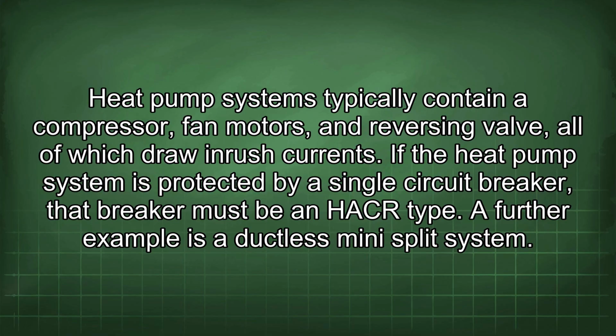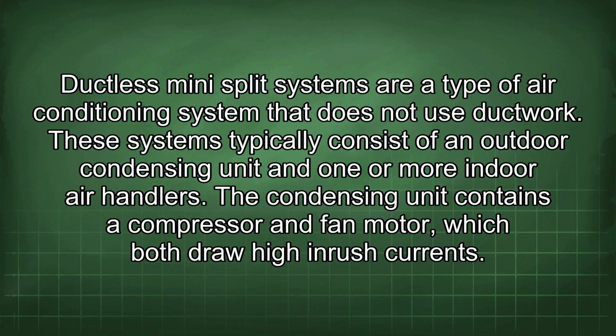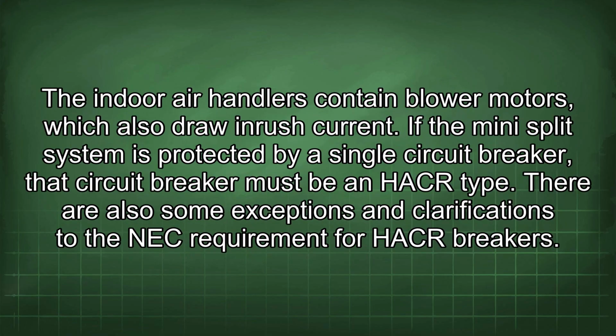A further example is a ductless mini-split system. Ductless mini-split systems are a type of air conditioning system that does not use ductwork. These systems typically consist of an outdoor condensing unit and one or more indoor air handlers. The condensing unit contains a compressor and fan motor, which both draw high inrush currents. The indoor air handlers contain blower motors, which also draw inrush current. If the mini-split system is protected by a single circuit breaker, that circuit breaker must be an HACR type.